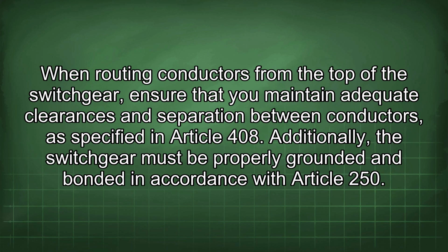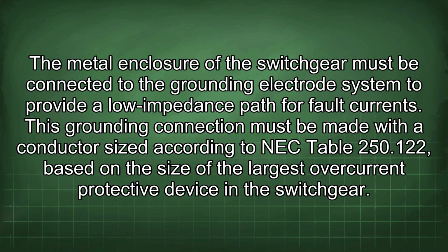When routing conductors from the top of the switchgear, ensure that you maintain adequate clearances and separation between conductors, as specified in Article 408. Additionally, the switchgear must be properly grounded and bonded in accordance with Article 250. The metal enclosure of the switchgear must be connected to the grounding electrode system to provide a low impedance path for fault currents. This grounding connection must be made with a conductor sized according to NEC Table 250.122, based on the size of the largest overcurrent protective device in the switchgear.